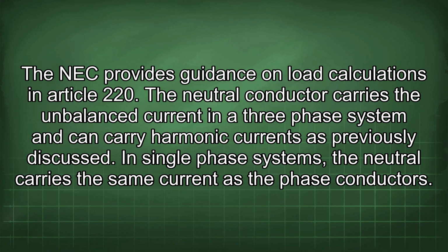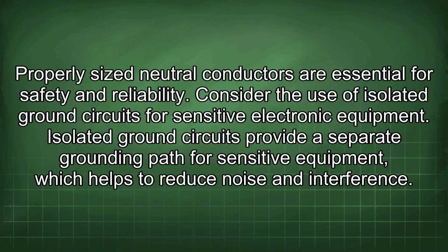The neutral conductor carries the unbalanced current in a three-phase system and can carry harmonic currents as previously discussed. In single-phase systems, the neutral carries the same current as the phase conductors. Properly sized neutral conductors are essential for safety and reliability.